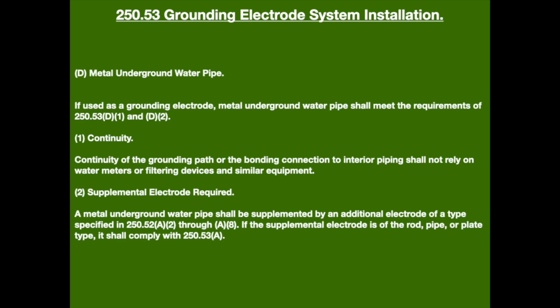Metal underground water pipe. If used as a grounding electrode, metal underground water pipe shall meet the requirements of 250.53(D)(1) and (D)(2). Continuity. The continuity of a grounding path or the bonding connection to interior piping shall not rely on water meters or filtering devices and similar equipment. Supplemental electrode required. A metal underground water pipe shall be supplemented by an additional electrode of a type specified in 250.52(A)(2) through (A)(8). If the supplemental electrode is of the rod, pipe, or plate type, it shall comply with 250.53(A).